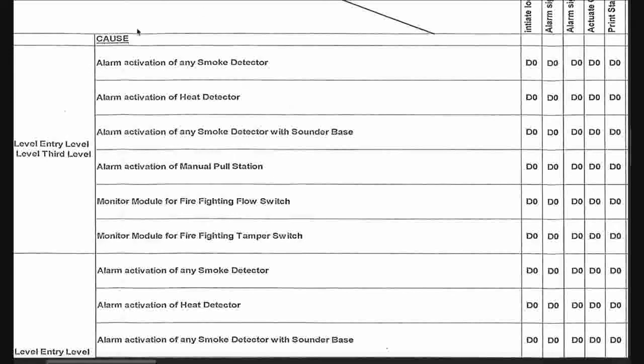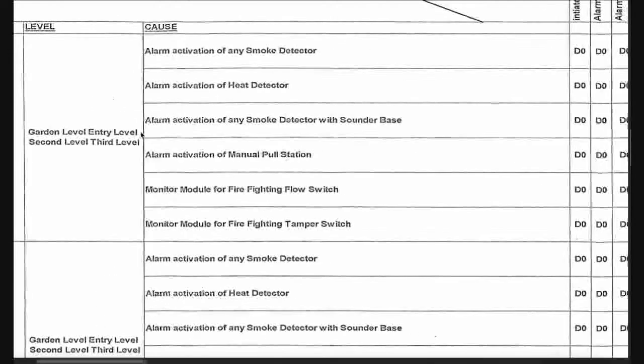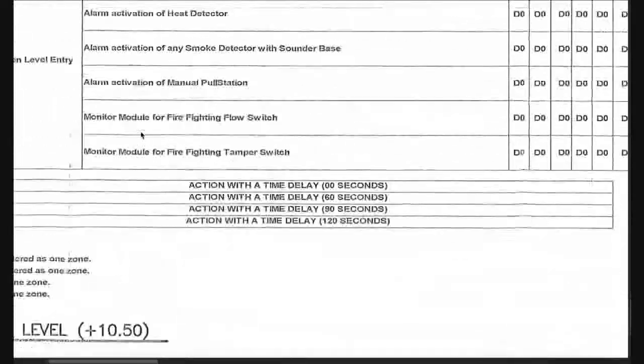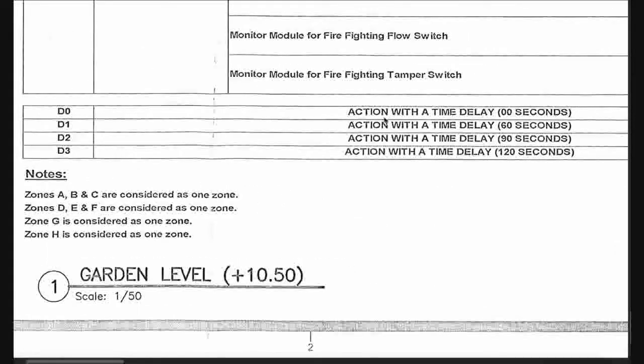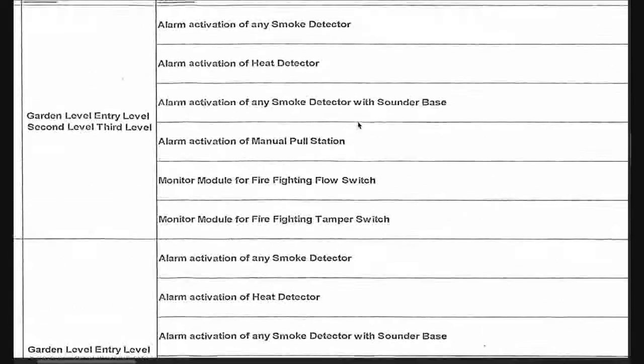Here we have a legend. D0 means action with a time delay of 0 seconds — the action shall be activated immediately. D1 means the action shall be delayed 60 seconds. D2 means the action shall be delayed by 90 seconds. D3 means the action shall be delayed by 120 seconds.